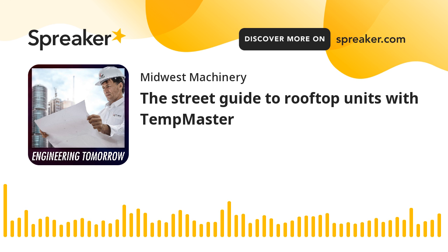The other thing from a redundancy perspective on the refrigeration system is all our units have 2 circuits of refrigeration. So if one circuit goes down, the other circuit can pick up and continue to deliver conditioned air to the space. On the flip side, on the gas heating, we have modules of gas heat, and each unit has 2 or more modules. So if one module fails, the other module can pick up and continue to deliver conditioned air to the space.